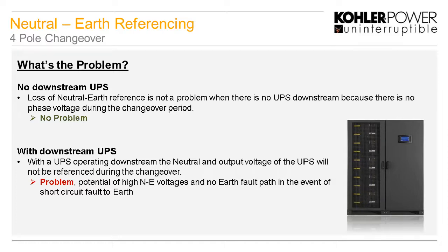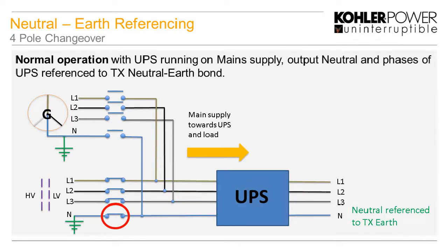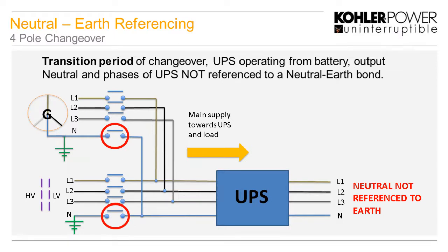So that does become a problem because there's no earth fault path in the event of a short circuit on the output of the UPS. So we can see this now in these diagrams. In normal operation, the output of the transformer, UPS, the output neutral is referenced to the TX of the supply. So during that changeover, the UPS now is operating, it's outputting voltage, but that neutral is not referenced to any input earth. Okay, now in any UPS there is no neutral earth bond. Even if it's an old transformer-based UPS or transformerless, there is no neutral earth bond within the UPS.